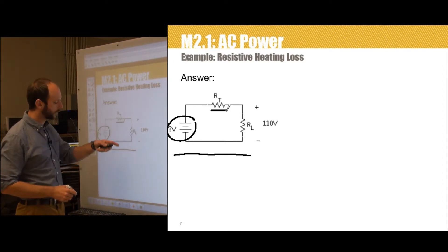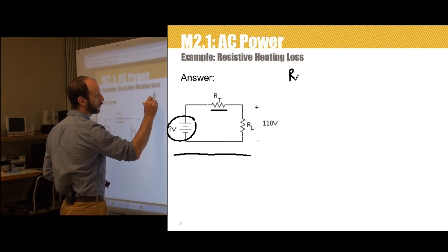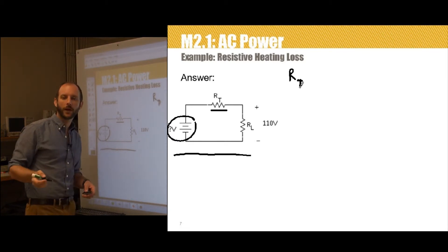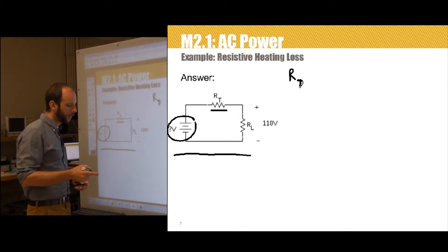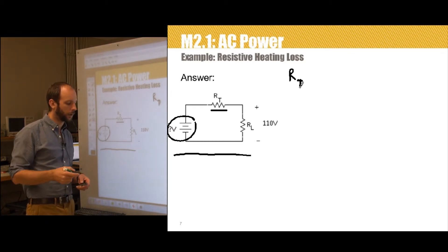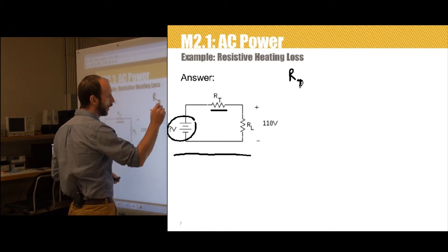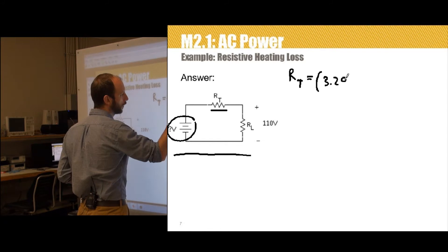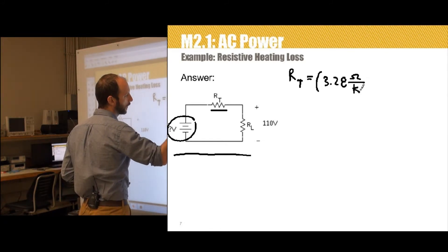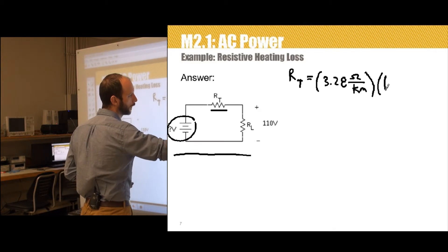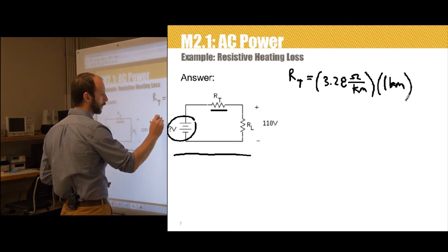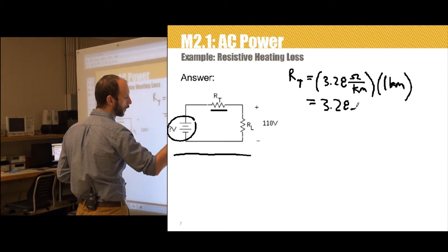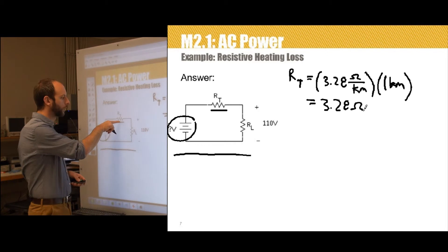Let's start calculating some of these unknowns. The total resistance of the distribution cable, R sub T, is relatively straightforward — we just multiply the total length of the cable by the resistance per unit length. That gives us the transmission line resistance: 3.28 ohms per kilometer times 1 kilometer of cable, so the total transmission line resistance is 3.28 ohms. That cable looks like a 3.28 ohm resistor.